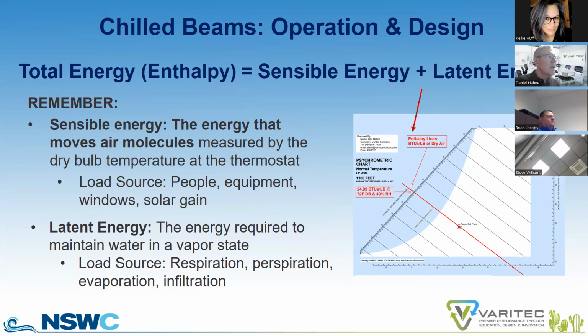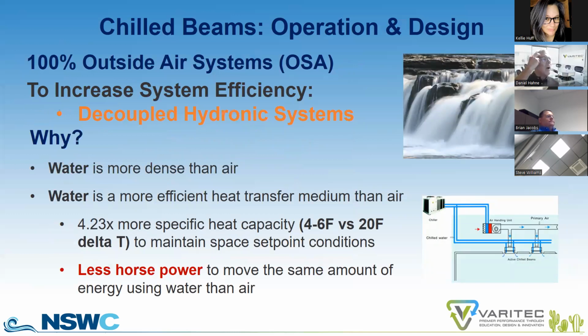What are the sources of sensible heat energy in a building? People, equipment, windows, solar gain, all of those items within a building. And then what adds to the latent energy? Respiration from occupants, perspiration, evaporation, and infiltration. So how can we shift the sensible load to a more dense heat transfer medium such as water? What if we decoupled the sensible load from the latent load that is otherwise seen as the total load in an air handler cooling coil? What if we decoupled that and then handled the sensible heat transfer with chilled water and handled the latent energy component with the air handler serving a building?